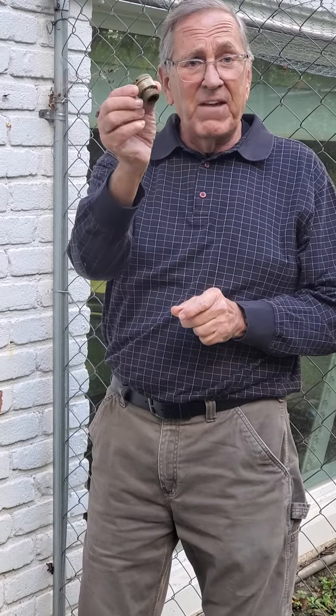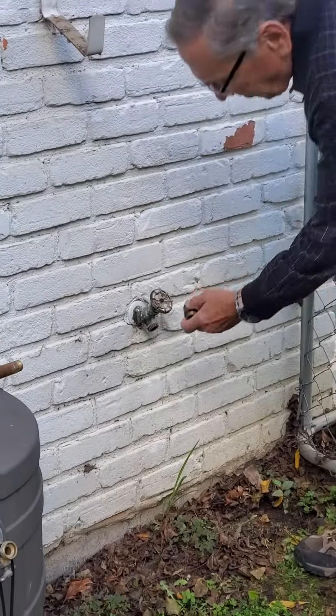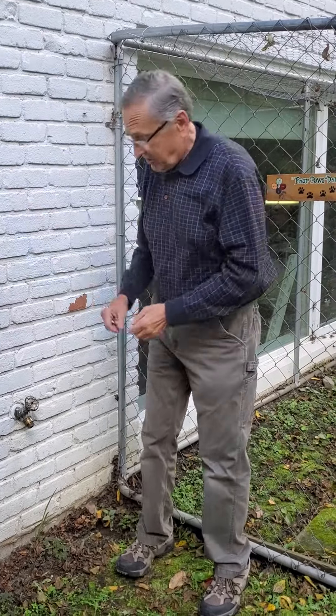By code, they should have this on it. It's called a vacuum breaker, and a vacuum breaker just screws right onto your hose bib and your hose goes onto that, and it prevents back-siphoning of water. What that means is if your garden hose is lying in the ground or in a puddle, and the fire department turns on a hydrant or a main breaks, you won't be sucking contaminated water out your kitchen sink.